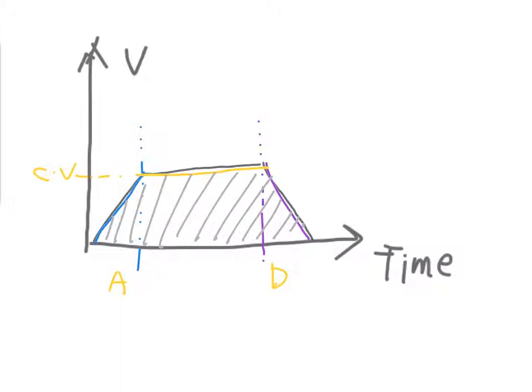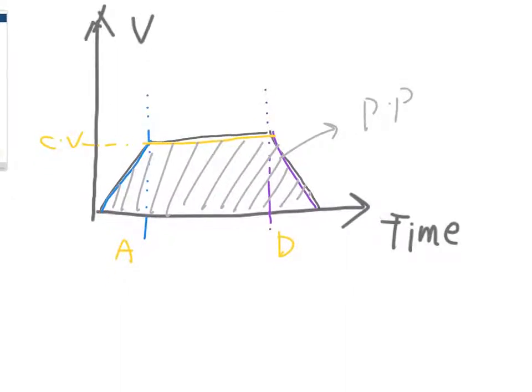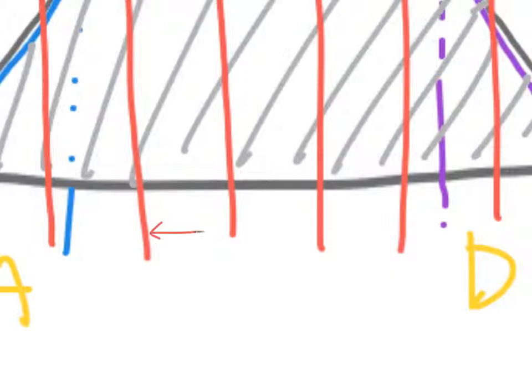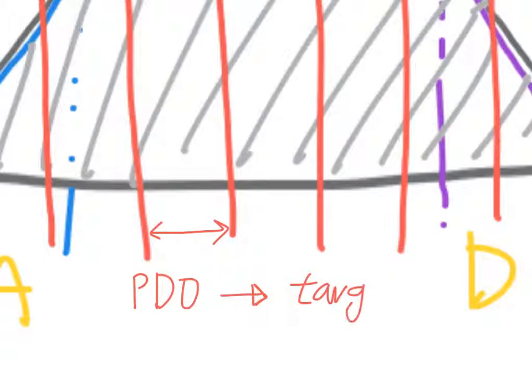This area means the position or moving distance, and this will be determined by the PP mode setting. Regarding the CSP mode, there is a cycle of PDO update. This is the PDO update cycle, and at every PDO cycle the driver receives the target position.